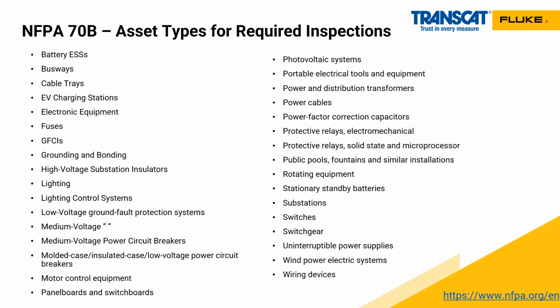On every device that requires insulation testing, you're going to have a nameplate sitting on it. If you looked at a nameplate on a motor, it's going to say operating voltage, operating current, operating temperature. It'll be right on there. And typically for a motor or even a transformer, it'll be either 40 or 50 degrees Celsius. Typically everything's done in Celsius, not Fahrenheit.